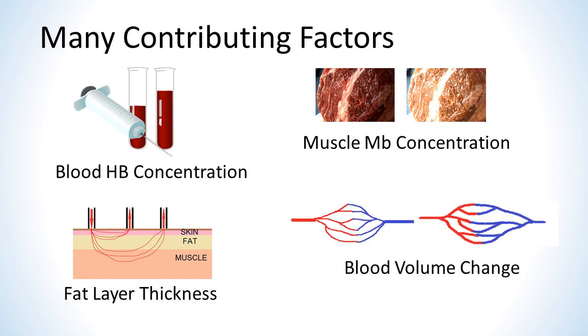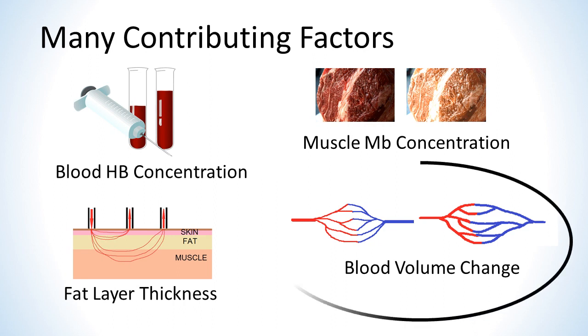Fourth is the volume of blood in the muscle — the more blood present, the higher the THB reading. All other factors remain effectively constant for a single sensor location over the duration of a typical assessment or workout. However, blood volume can change rapidly and dramatically depending on muscle tension and vascular tone, and these changes can help us infer what's going on with blood flow.